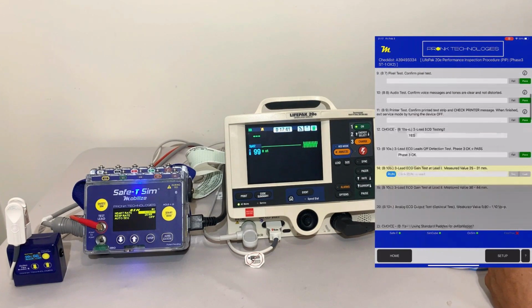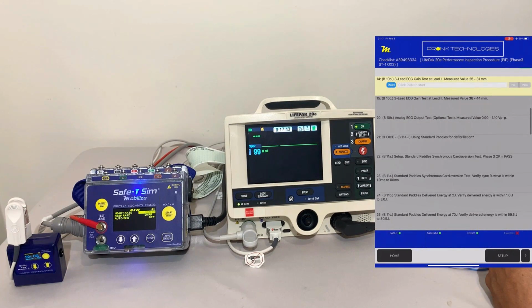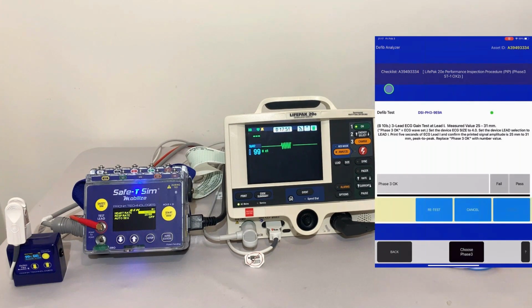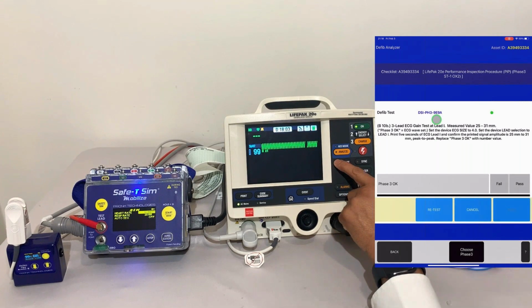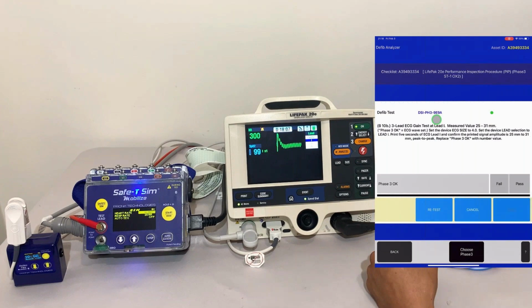The next test is wanting us to do a gain test. We want to make sure that the ECG gain is correct, as it's making sure that the amplitude is correct. We're going to go ahead and run that test. Again, the phase 3 is going to be generating a sine wave. My instructions here want me to do this test on lead 1. I want to make sure that I'm in lead 1 here. We'll go ahead and change that, and I'm in lead 1.